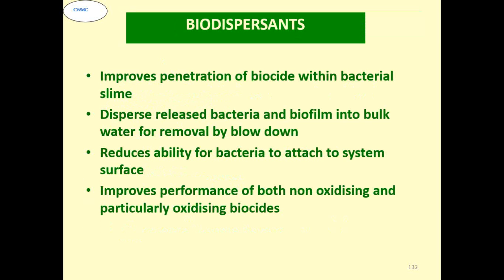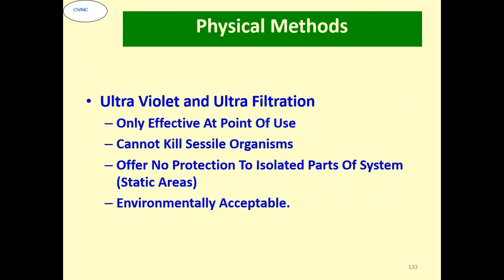Okay. Many times these biocides are supported by biodispersants, which are generally some kind of surfactant. Those help improve the efficacy of the biocide in attacking the bacteria and killing them. It also helps in cleaning the system, because it helps in removing the dead mass from the system. Some physical methods are ultraviolet and ultrafiltration. Normally these are used in a small system, not in a very large industrial area.